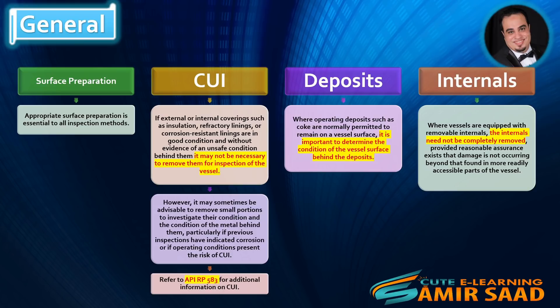If external or internal coverings, such as insulation, refractory linings, or corrosion-resistant linings are in good condition and without evidence of an unsafe condition behind them, it may not be necessary to remove them for inspection. However, it may sometimes be advisable to remove small portions to investigate their condition and the condition of the metal behind them, particularly if previous inspections have indicated corrosion or if operating conditions present the risk of CUI. Refer to API RP 583 for additional information on CUI.